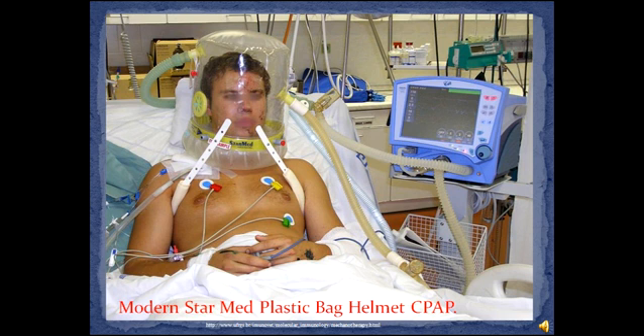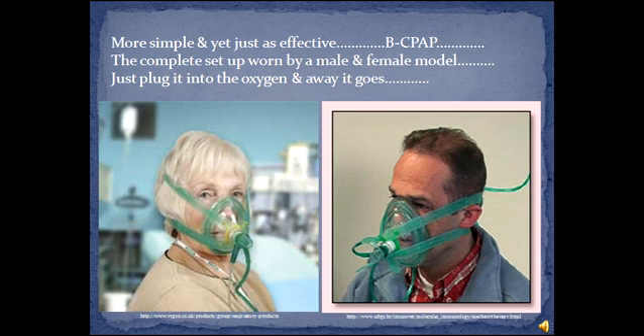The Boussignac CPAP system was first used in 1973 on Boeing 707 crash victims suffering severe respiratory distress from smoke inhalation, transported to Henri Mondor Hospital in Paris, where inventor anaesthesiologist Dr. Georges Boussignac was in charge of the intensive care unit. He secured plastic bags over the victims' heads and supplied high-flow oxygen with low pressure inside the bags, with an outlet hose in an 8 to 10 centimetre column of water. The system maintained pressure against airway structures, keeping them open to facilitate a reduction in the work of breathing.